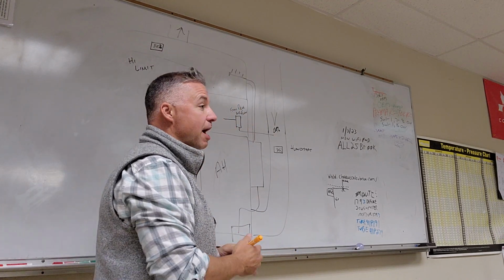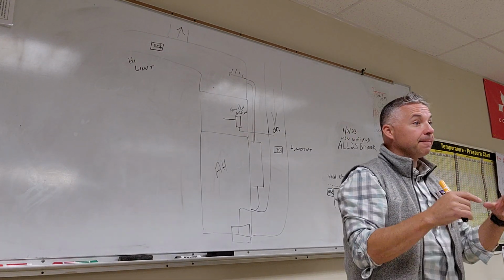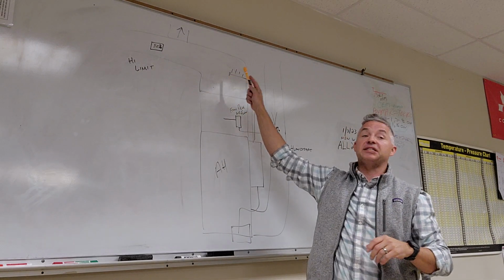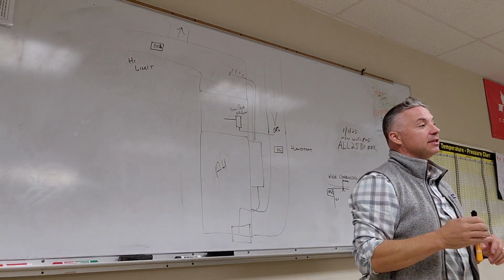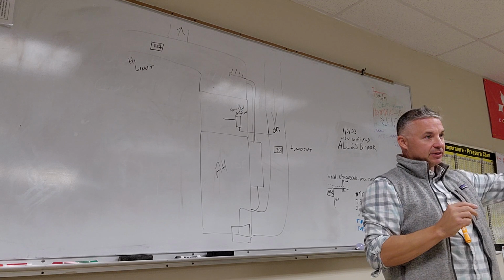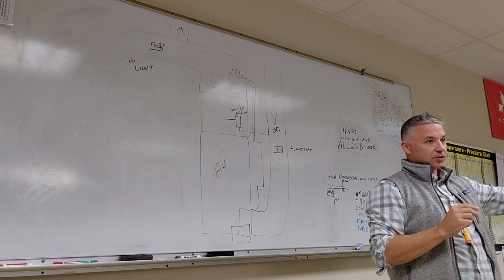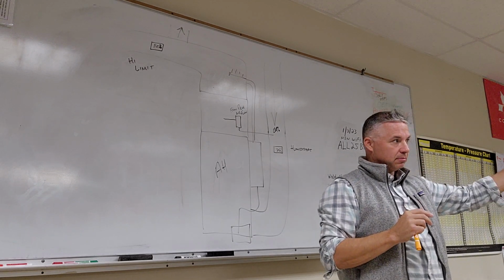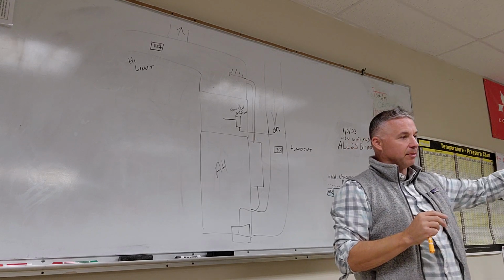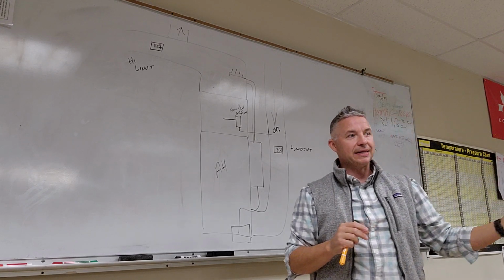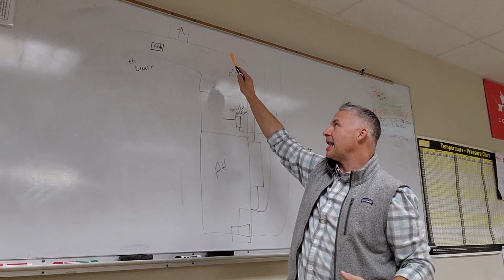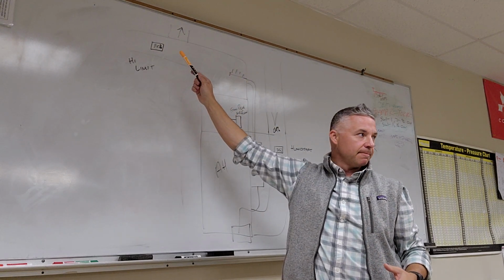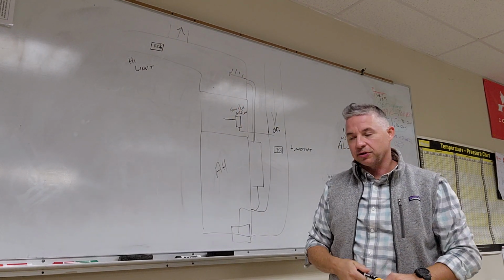With no airflow, you have actual steam. With airflow, what happens to that steam when it leaves the steam distributor or the steam nozzle is that moisture is instantly atomized, okay? So it's not wet anymore. It's atomized in the airstream. If you don't have airflow, you have wet steam. Wet steam is, again, now damaging our ductwork, causing all kinds of potential problems with our system.